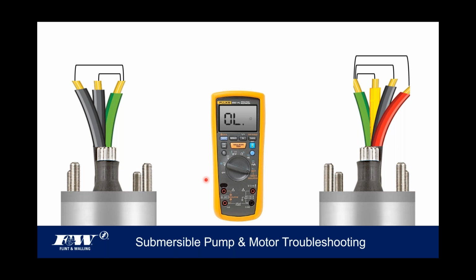All right, and here this is pretty black and white. If there's no resistance, in other words, I'm still showing infinity on my meter, I'll tell you that there's no ground. That's black and white. I'm not telling you the motor's good. I am telling you that it's not grounded. So if there's no resistance, there's no ground. On the other hand, if you get any resistance, even small amounts, any resistance at all will indicate a ground. So that's a pretty black and white test to run with a multimeter for the simple purpose of determining whether you've got a motor that's grounded or not, right?